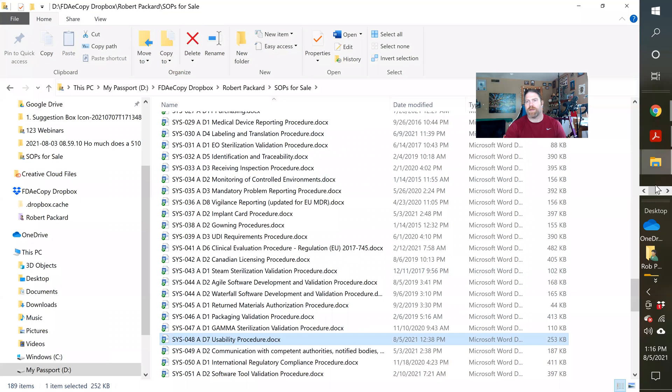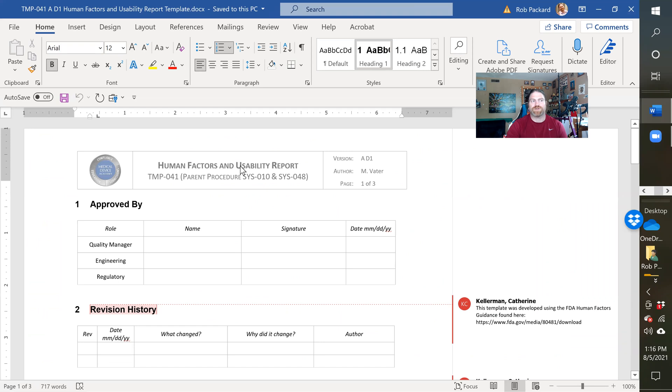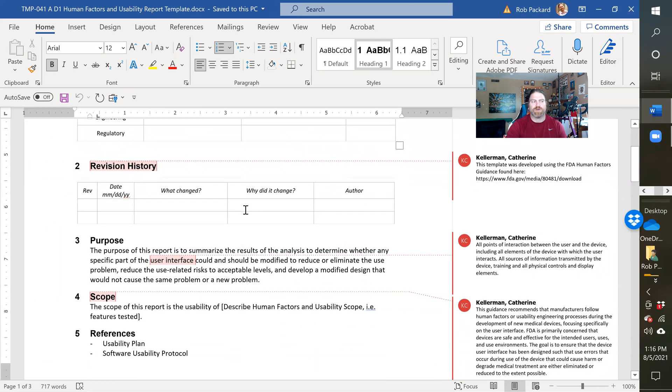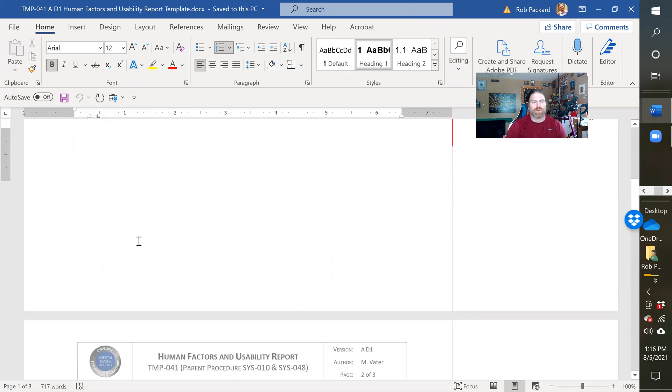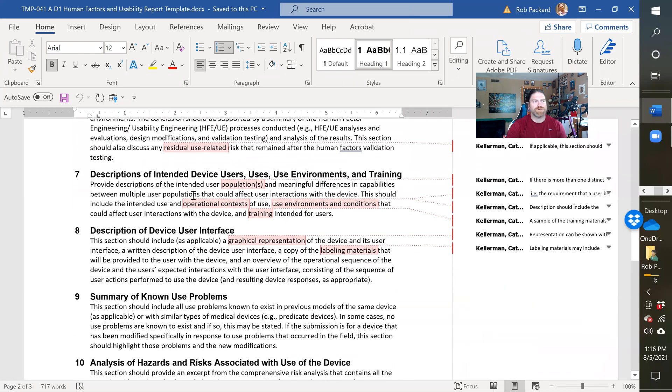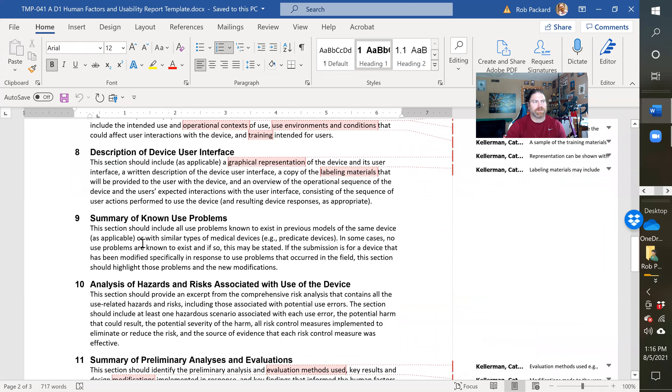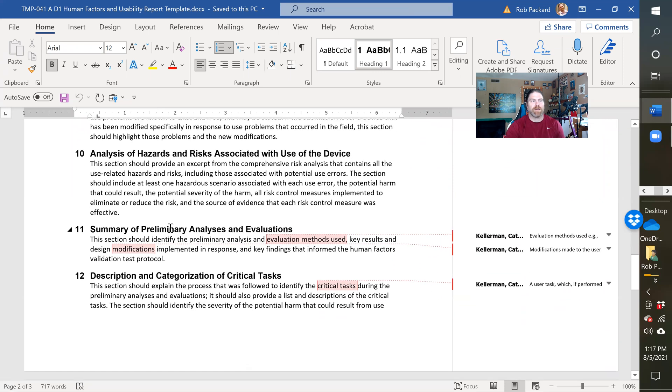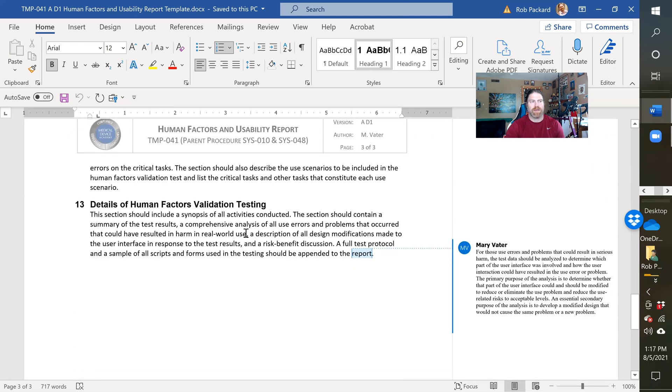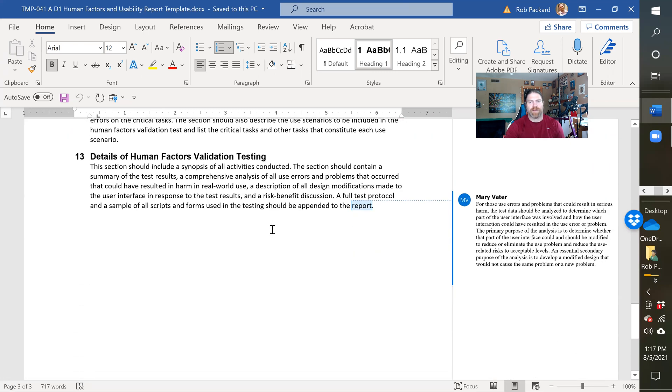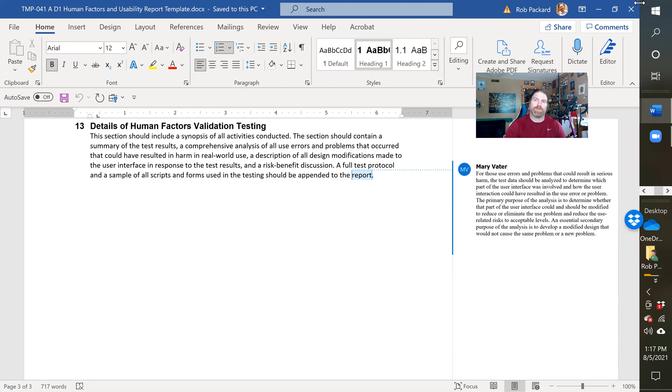Let's see what else do we have here. We have the human factors and usability report that you would publish after you've finished your usability study. This is what should be in the actual report. So conclusion, description of the devices, summary of known problems, this would be from existing MAUDE databases or other post market surveillance activities, hazards preliminary analysis and evaluations, categories of critical tasks, and then the human factors evaluation. So this would be the report you'd submit to the FDA after you're all done, but they often want to see a copy of the protocol that we reviewed previously.